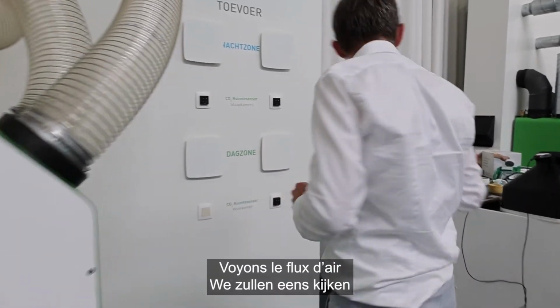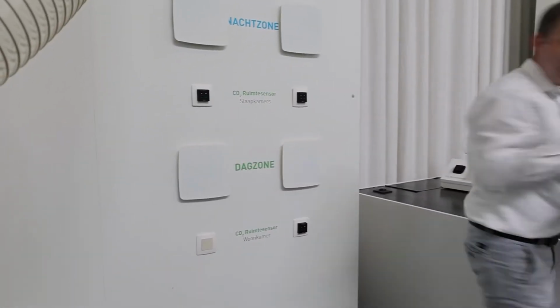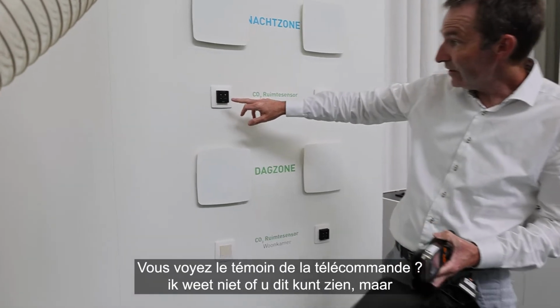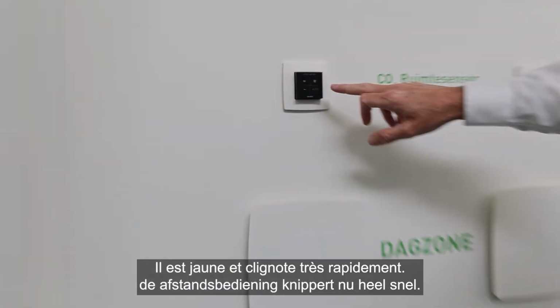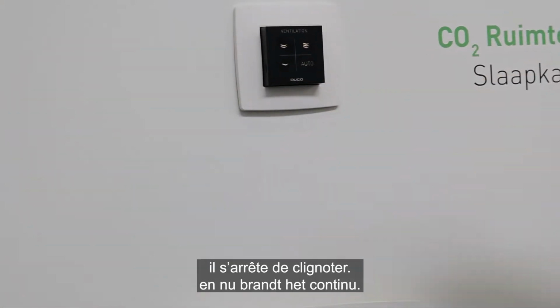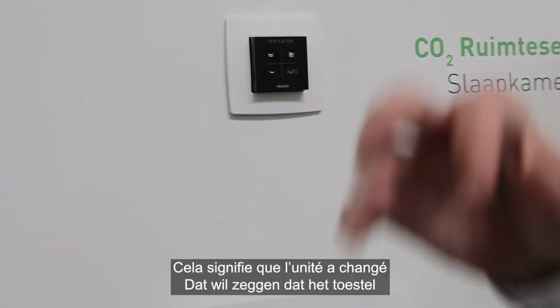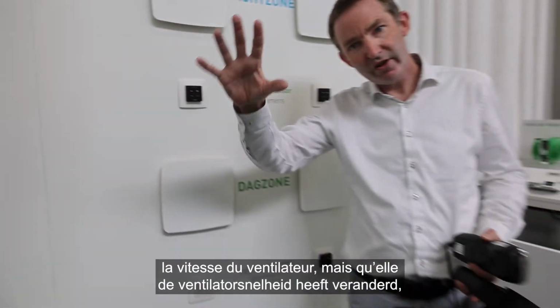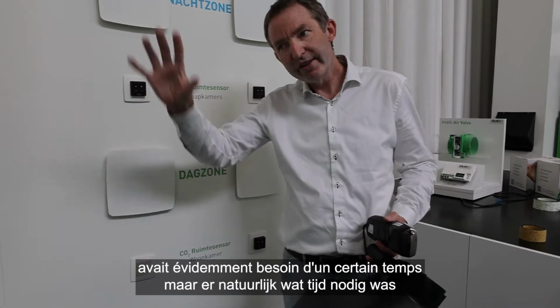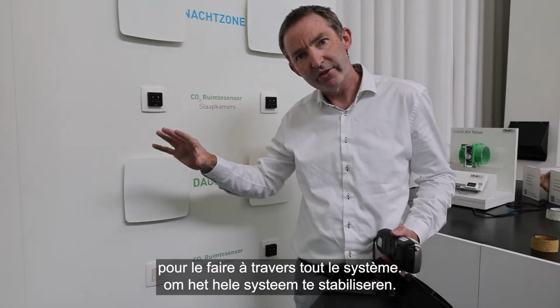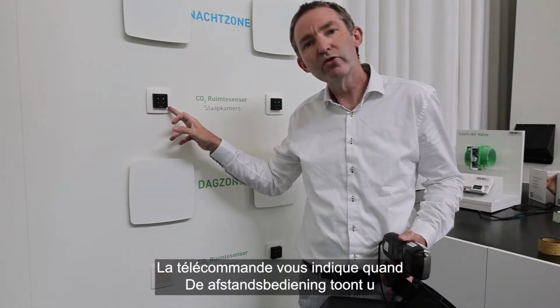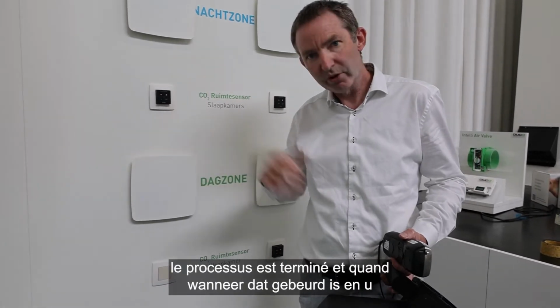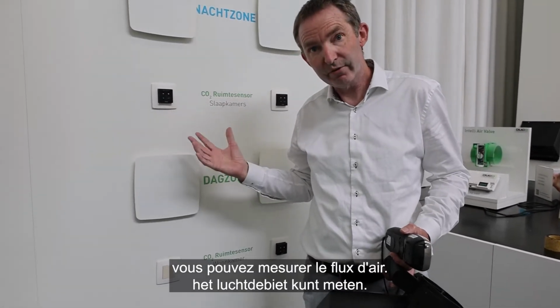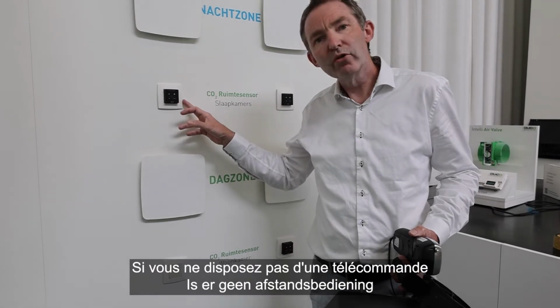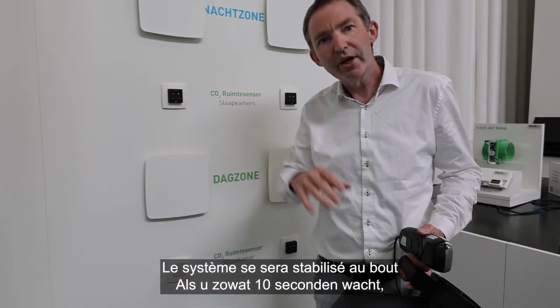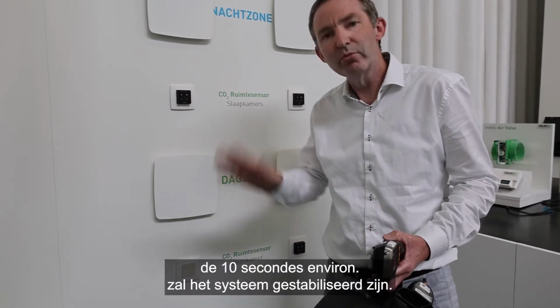We will see how much airflow we have now. By the way, which is interesting, I don't know if you can see, but the remote is blinking very fast now. It's blinking yellow and now it's stable. So this means that actually the unit has changed the fan speed, but it obviously needed time to stabilize throughout the system. Okay, the remote control gives you an indication when this is done and when you can actually start measuring the airflow. If you don't have a remote control in the neighborhood, don't worry. If you wait approximately 10 seconds, the system will have stabilized.